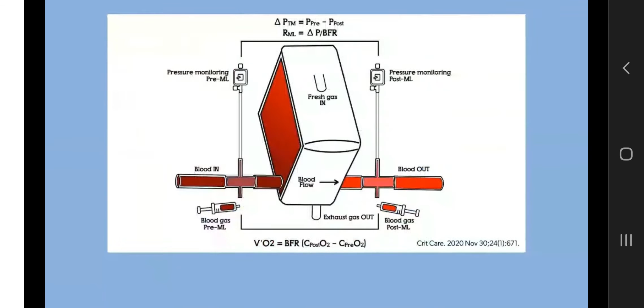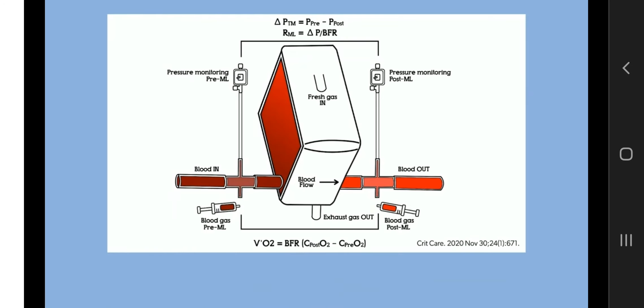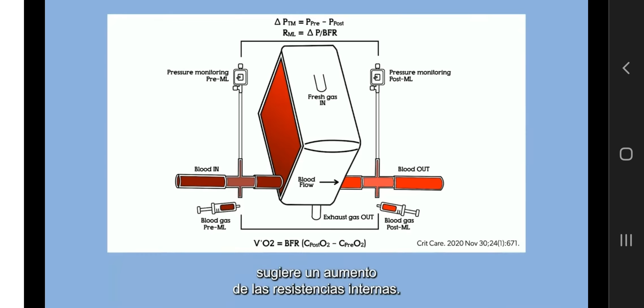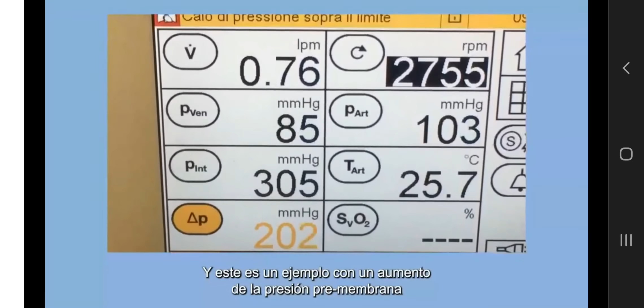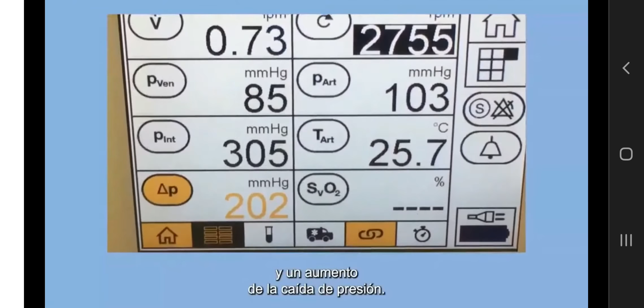Check circuit pressures and resistances. Thrombosis impairs blood flow through the membrane lung, so the membrane pressure drop, the pressure gradient between the pre-membrane pressure and the post-membrane pressure, is going to increase. Consider that pressure drop is affected by extracorporeal blood flow, so a more accurate parameter to evaluate is the ratio between pressure drop and extracorporeal blood flow, with a significant increase in this ratio suggesting increasing internal resistances. And this is an example with increasing pre-membrane lung pressure, decreasing post-membrane lung pressure and increasing pressure drop.